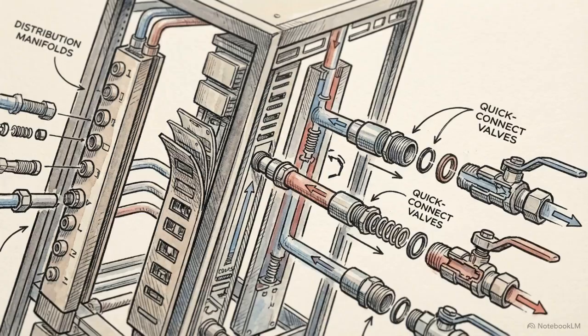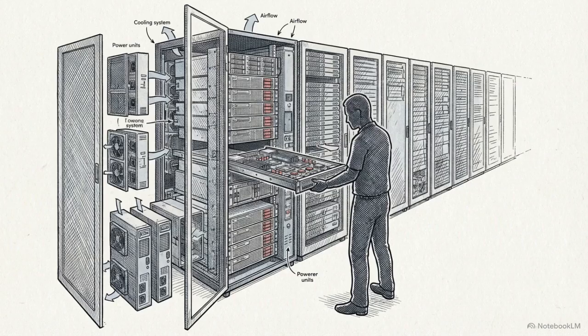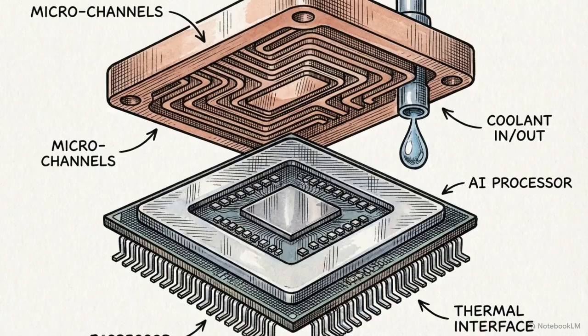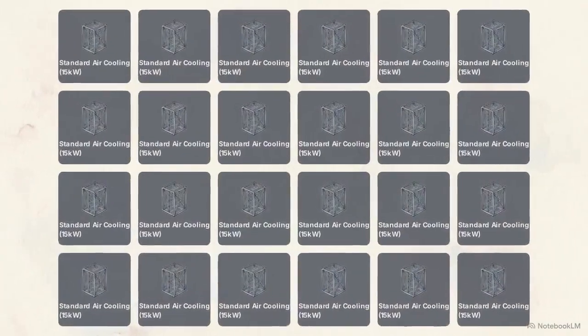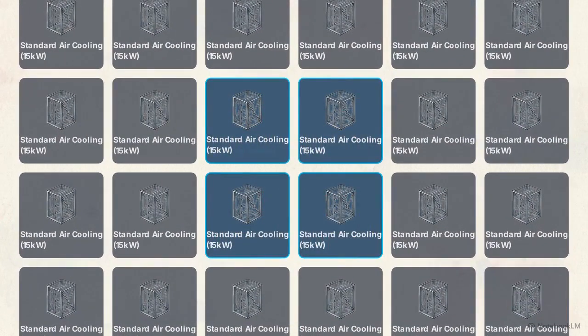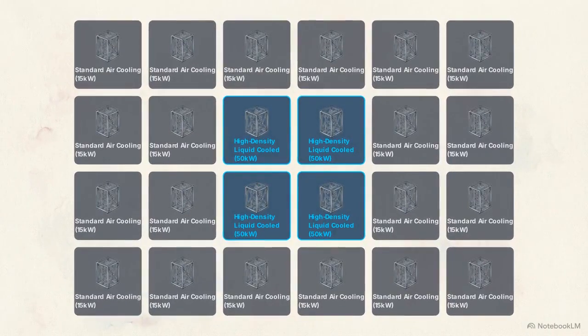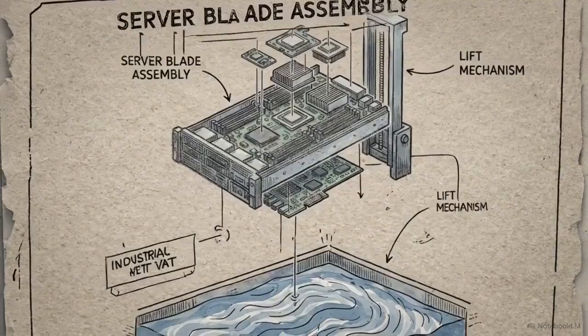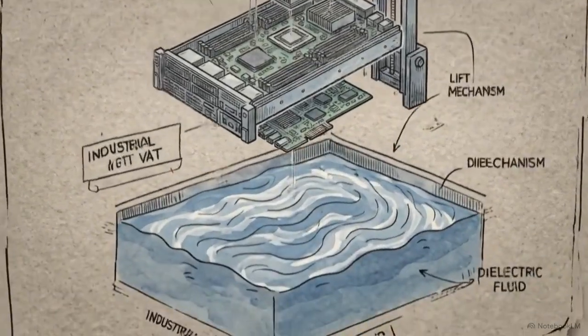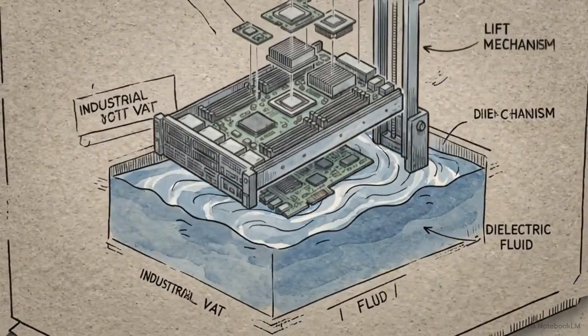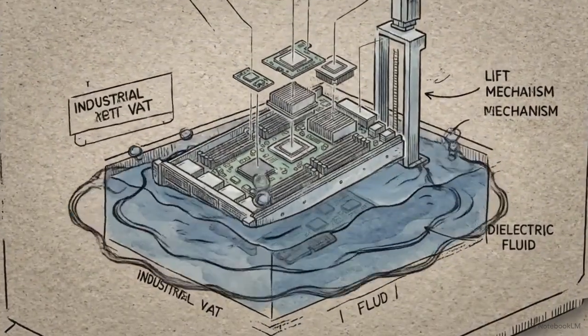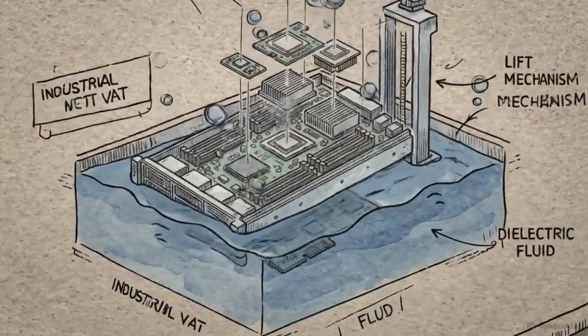It requires introducing liquid distribution manifolds directly into the server racks. However, it uses highly compatible server designs and allows your IT teams to maintain many of their familiar existing data center workflows. Direct-to-chip cooling acts as a precise surgical intervention. It lets you upgrade specific zones for high-density compute without executing a complete disruptive teardown of your existing facility. When your AI models push rack density requirements well beyond 50 kilowatts, targeted cold plates aren't enough. You have to move to complete fluid submersion.